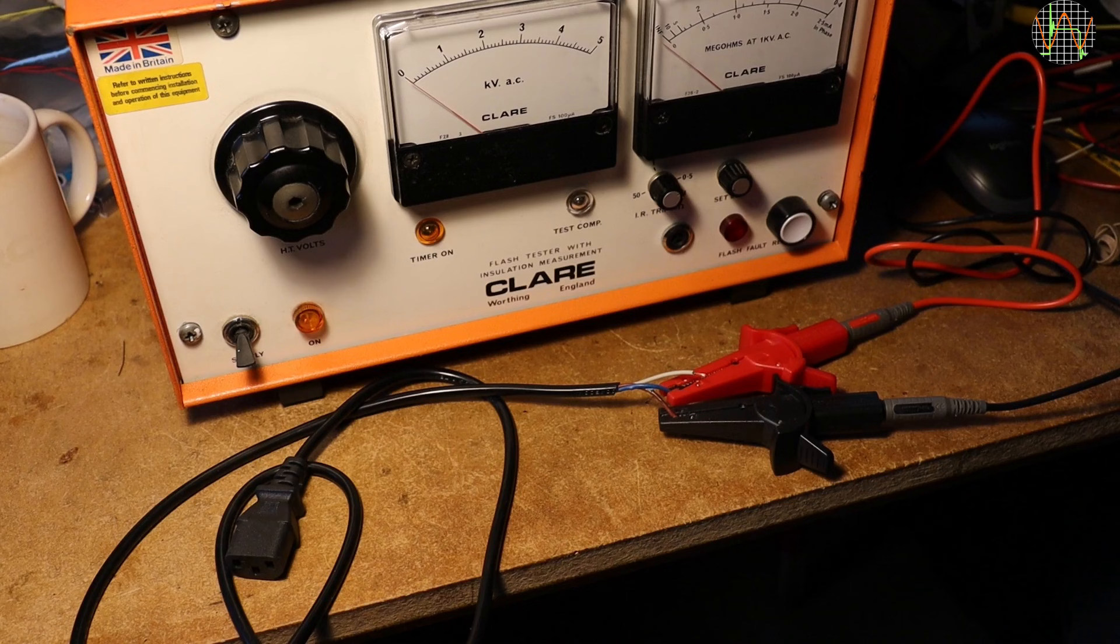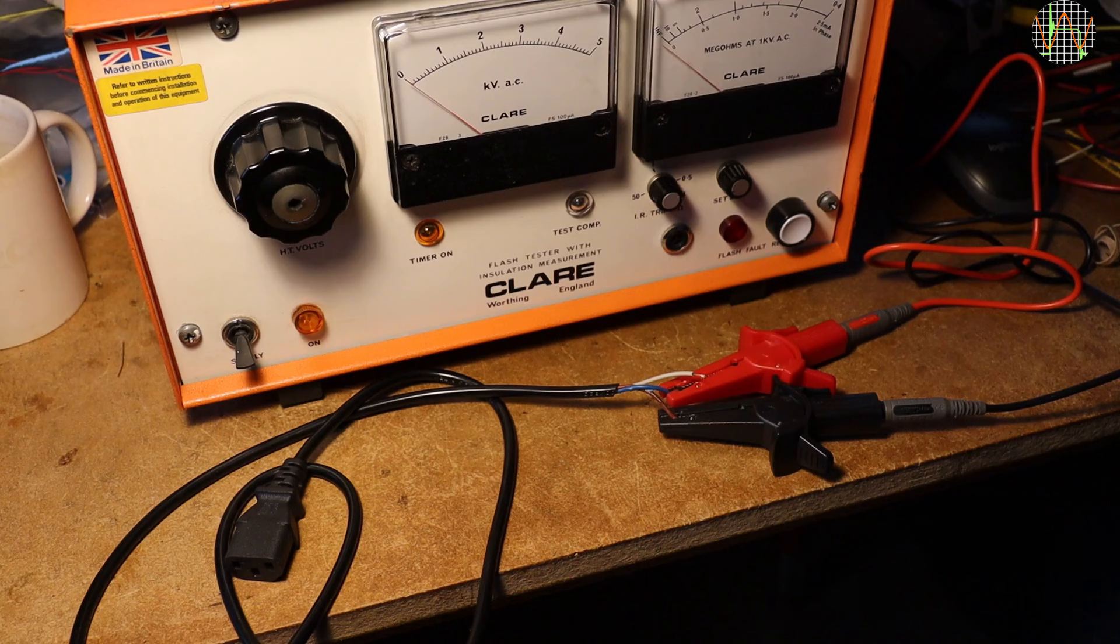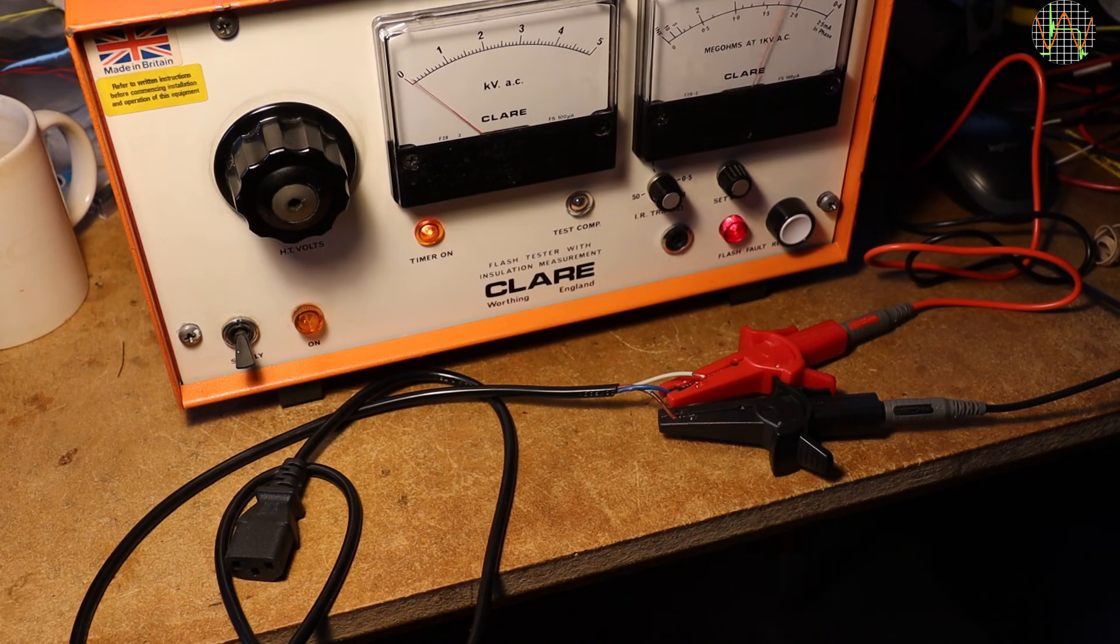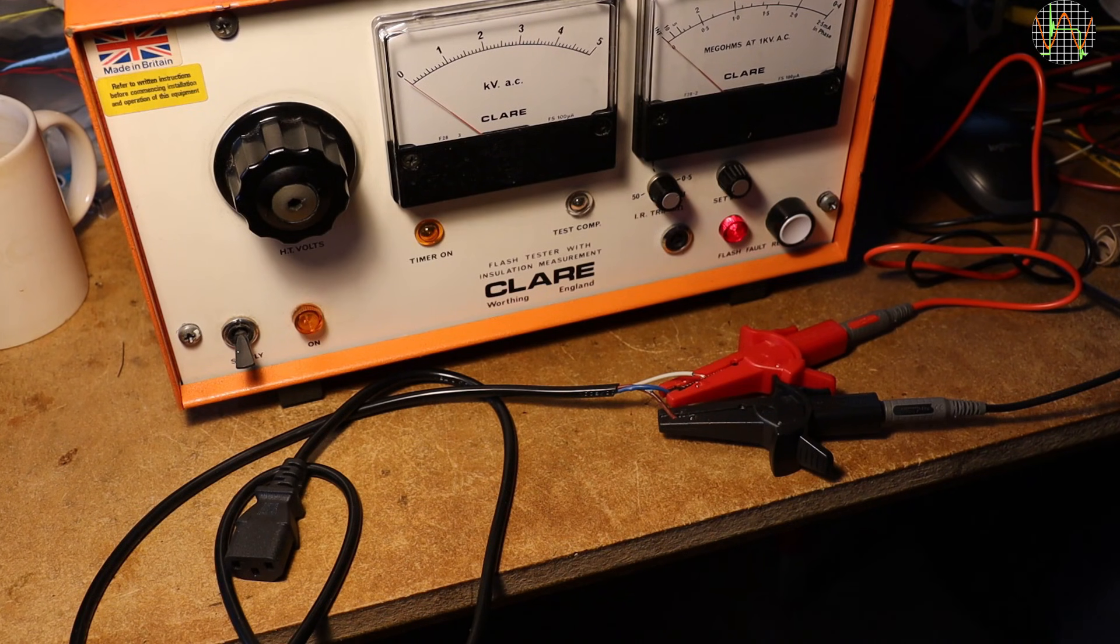But the Extech was limited to 1000V, and the Clare is not. I have set it to its full 5000V capability. And we have an immediate flashover. Somewhere inside the cable, I can also smell some burning.